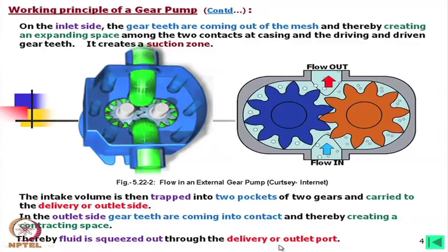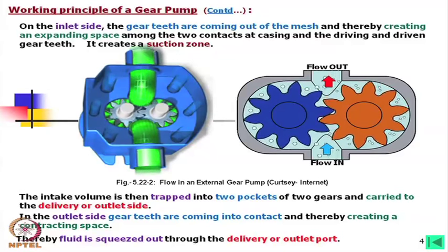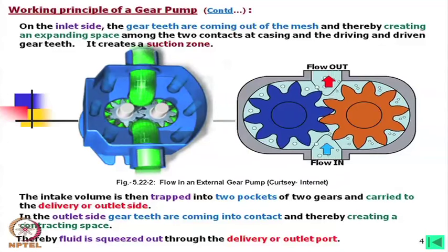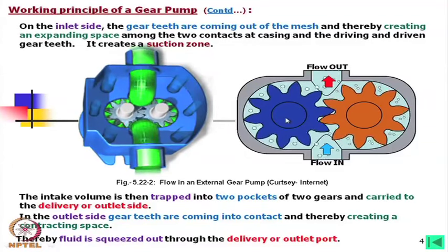In the case of a motor, this process is just the reverse. The oil will be pumped in from the high-pressure side, the volume will expand — so this will be the high-pressure side — and this will rotate in the same manner. The low-pressure oil will go out, and the pressure will be converted into force and torque. That torque can be taken out either from both gears or from a single gear.